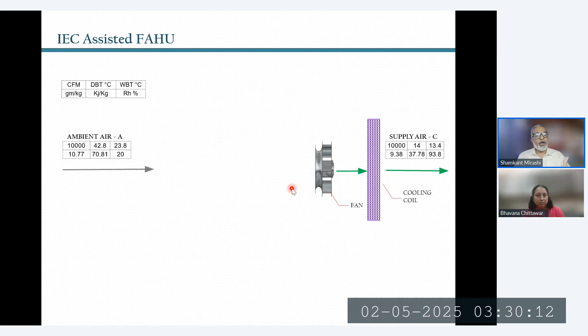And we say that we'll cool that air from 42 degrees to 30 degrees. So the coil is no more exposed to 42 degrees, but only to 30 degrees. So the coil will send a signal to the chiller saying, I'm getting pre-cooled air, I don't need so much refrigeration flow now. So the coil is going to demand less chilled water. Why? Because now it is exposed to air which is pre-cooled. It is no more exposed to the ambient air of 42, 43 degrees, but only 30 degrees or so, and the coil is going to demand less.